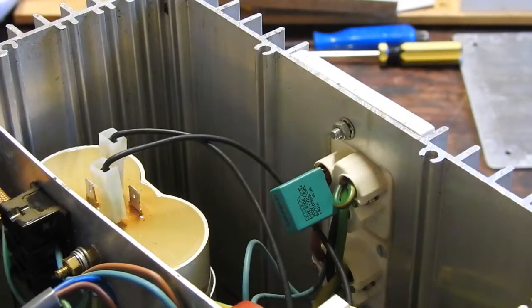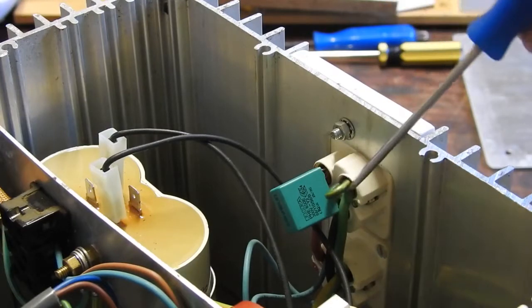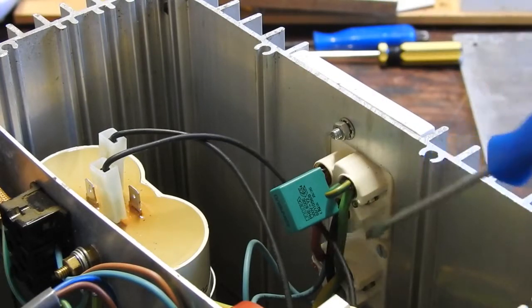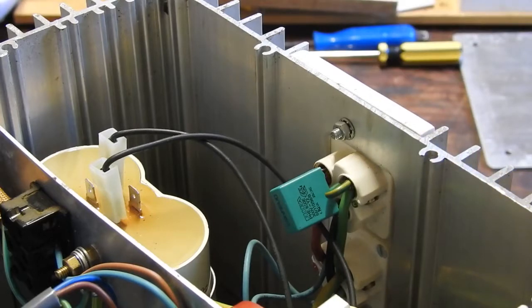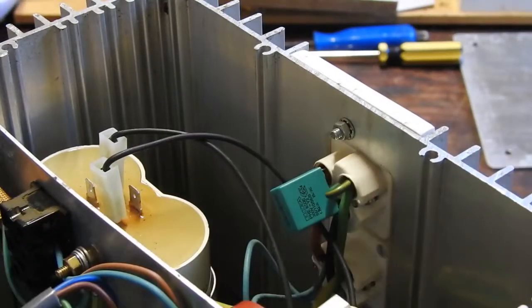I've replaced that capacitor and I've looped the earth back into itself, so that the neutral and the earth are separate, and this is now a true isolation transformer. Maybe I'll slap a little note on there saying that, but it's probably only going to be me that uses it. But I should put a note there in case someone else ever gets it and relies on the earth there. Okay, let's see what it does when it's plugged in.